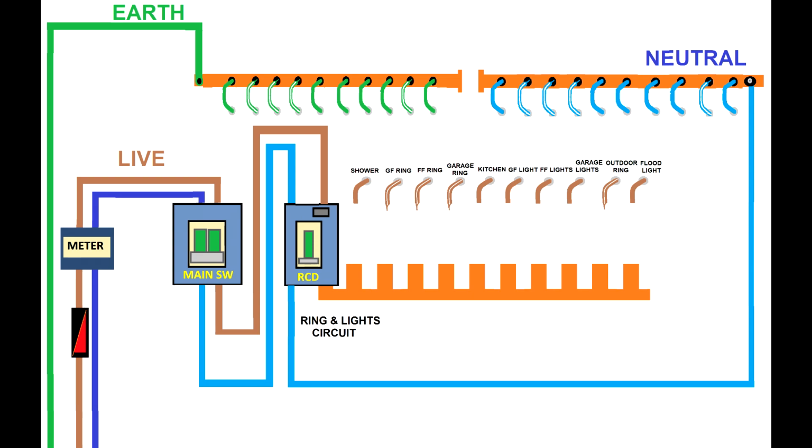In case you have a 32 amp circuit breaker, if you break the circuit to any socket or any point, you have to replace the 32 amp circuit breaker with a 16 amp circuit breaker. So you have to apply a derating factor, and you have to protect the wires, otherwise your installation might catch fire. Now let's talk about the economical issue.